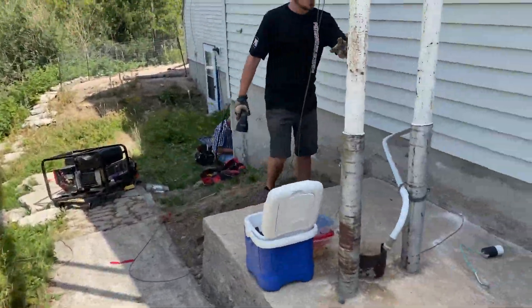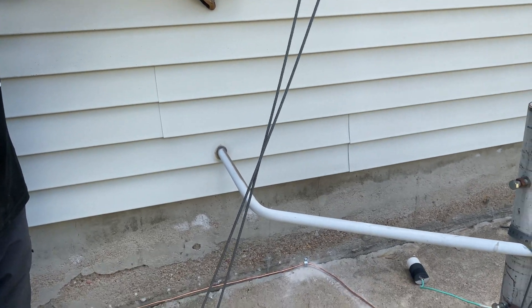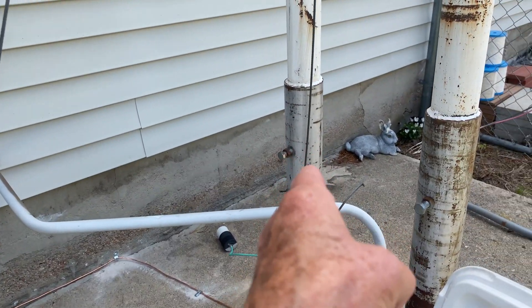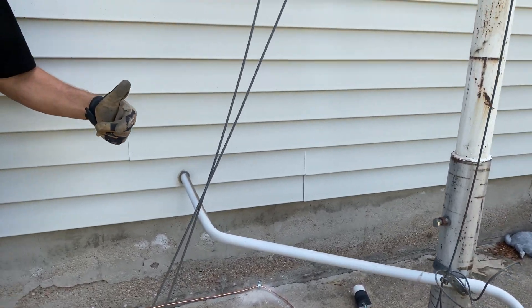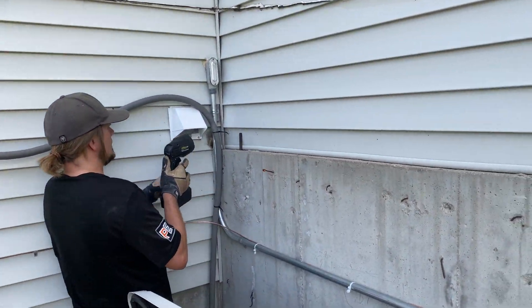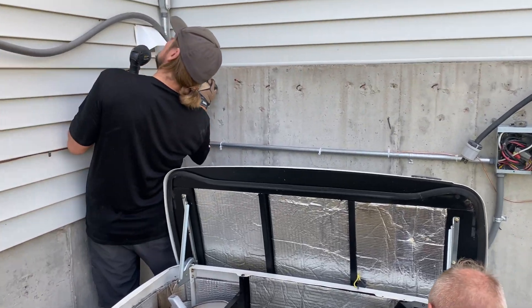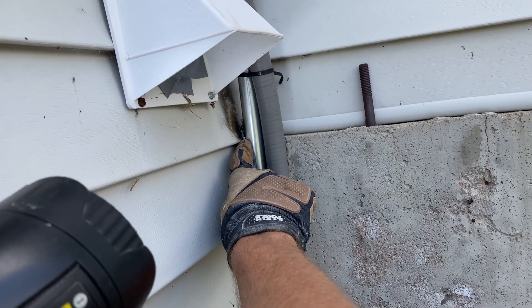Right where that windmill came in, there should have been power coming into a fusible disconnect. At 400 watts and 240 volts, even a 10-amp fuse would have done it, though a little fuse goes around 15 amps first. It was grounded but non-fused, so if it had been fused maybe it wouldn't have blown out the inverter. Down here is also where lightning hit — this is why I don't like plastic siding with metal trim. Right here you can see it arced; now that's grounded.